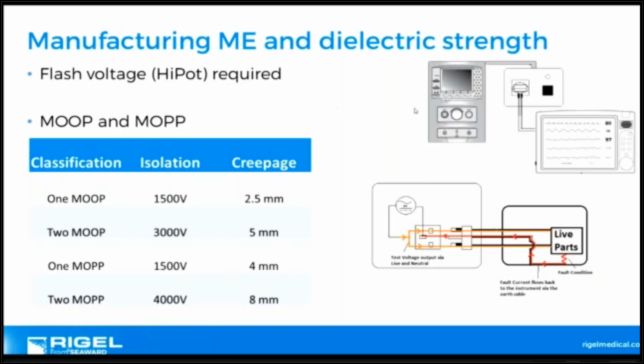Anyway, people are getting in touch, and we do have a brother or sister company, affiliated with Rigel Instruments and Seaward. We have a dielectric strength tester that produces 25 amps, up to 40 amps actually, and has dielectric strength up to 6 kV for DC, 5 kV for AC. And what we're trying to prove is that your means of operator protection and means of patient protection are isolated. So this creepage and this isolation is within the safe recommendations of 60601. So this is within the standard, this is within 60601.